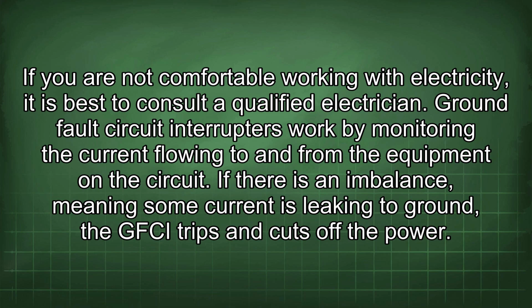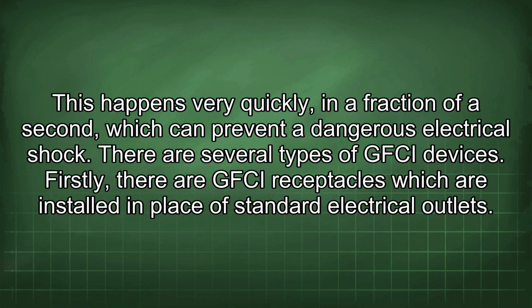Ground fault circuit interrupters work by monitoring the current flowing to and from the equipment on the circuit. If there is an imbalance, meaning some current is leaking to ground, the GFCI trips and cuts off the power. This happens very quickly, in a fraction of a second, which can prevent a dangerous electrical shock.